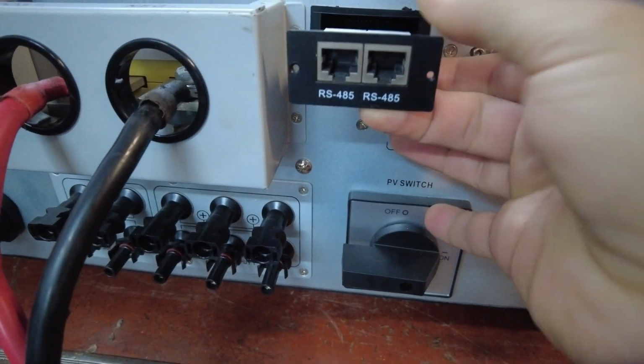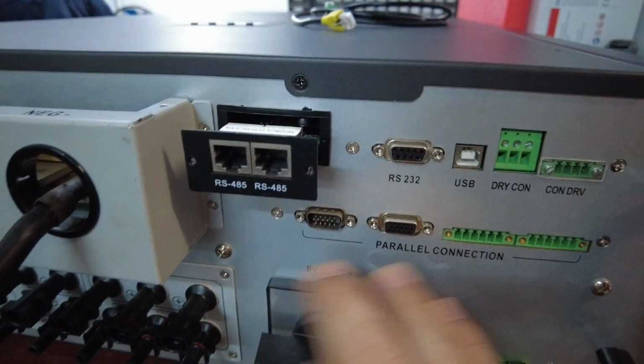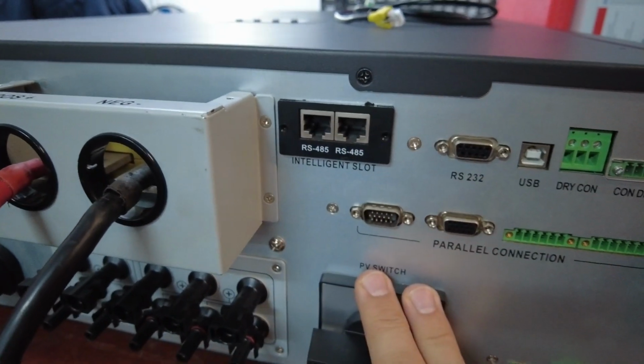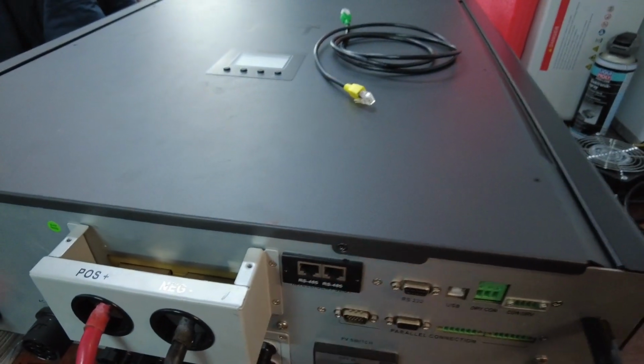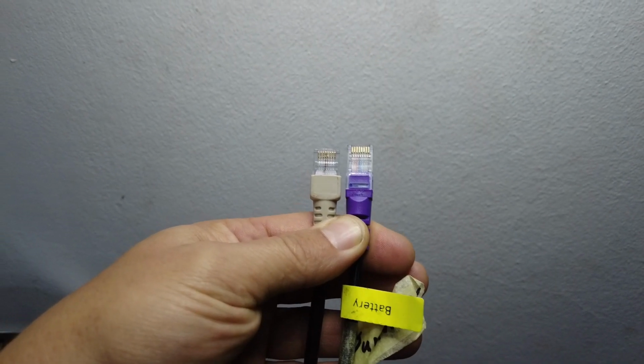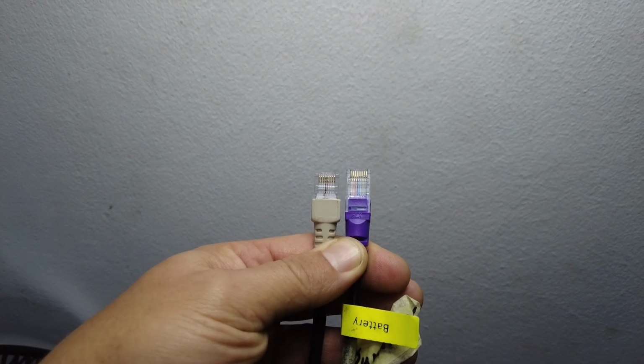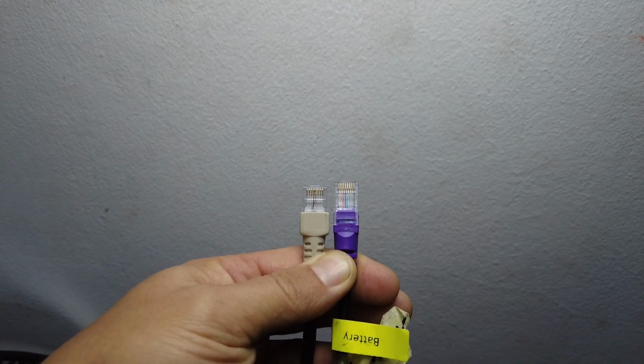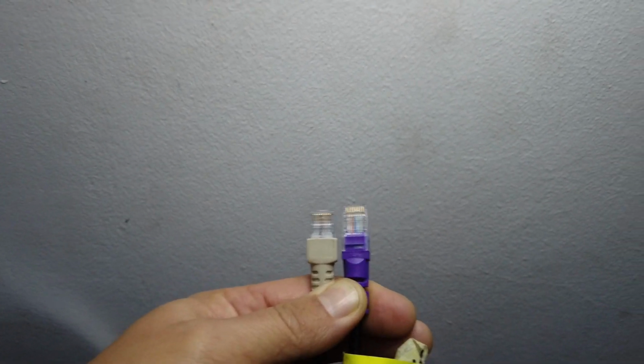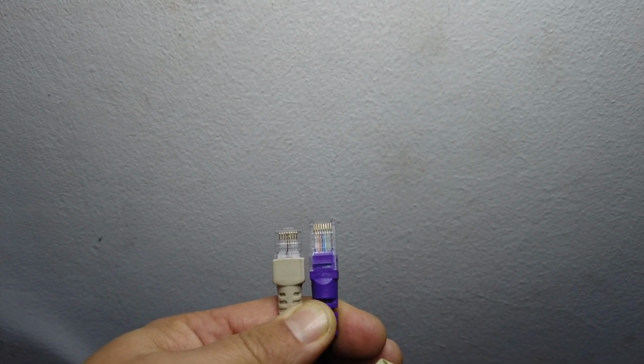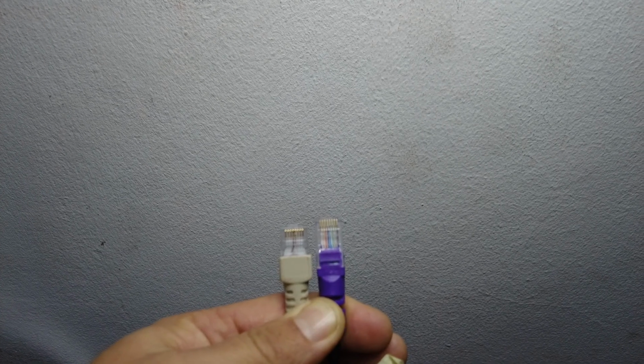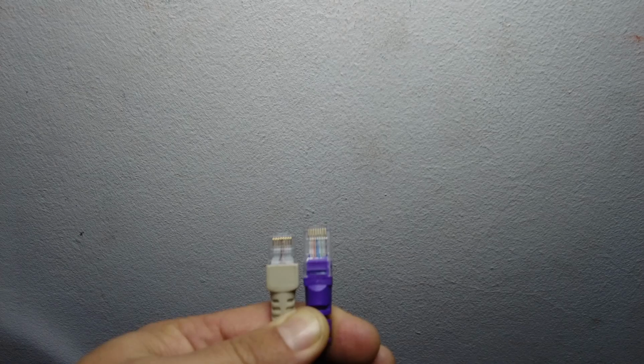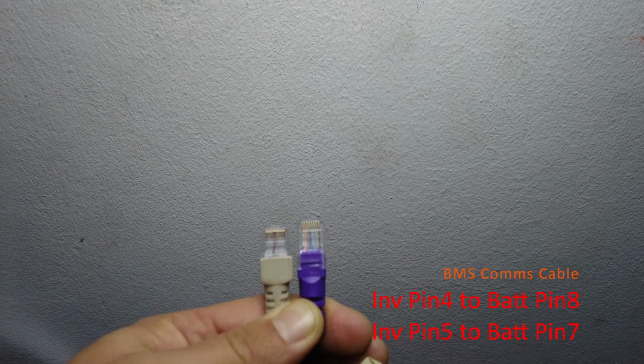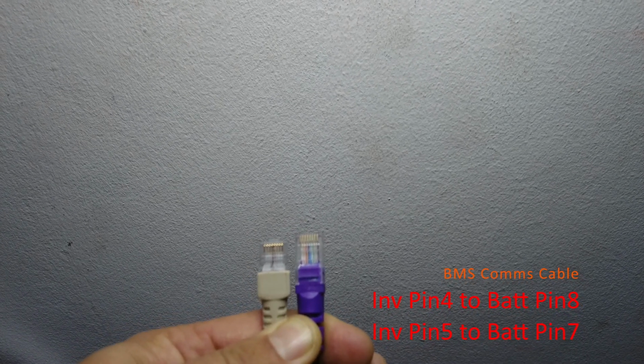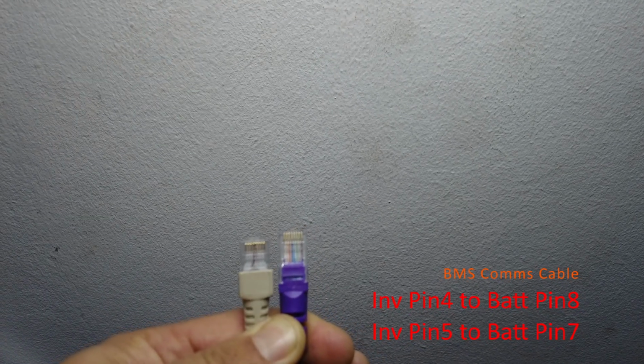So now that the dips are set properly, you will unfortunately not see clearly in this card slot, but there are grooves that you need to slot this card into. Once it's set in those grooves, you can just push it all the way in and insert your screws as well. To establish BMS communication between the inverter and the battery for this setup, you need to make the following BMS communications cable. The grey plug to the left is for the Modbus card on the inverter, and then to the right is the purple plug that leads to the battery. Inverter side pin number 4 will lead to battery side pin number 8, and then inverter side pin number 5 will lead to battery side pin number 7.